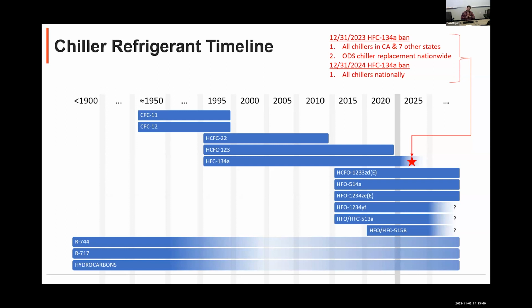That refrigerant was developed because one of the challenges with 1234ZE is that it's mildly flammable. It's classified by ASHRAE 34 as an A2L. There are certain things that you have to do to the refrigeration machinery room to install an A2L refrigerant. They are not nearly the measures that you would have to do to install a highly flammable refrigerant. There's just a few things that have to be added. 515B was developed. It is about, I think, 93% 1234ZE, but they mixed it with a little bit of HFC 227EA, just enough to get that flammability down to ASHRAE 34 class A1. So it eliminates the A2L issues. They're not very big issues. It raises the GWP to about 200. So that's the trade-off you can consider, but they basically work in the same equipment.